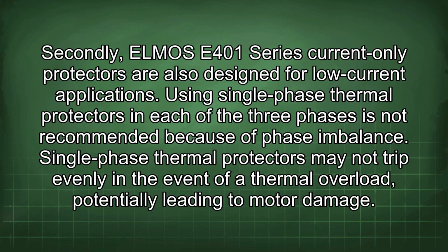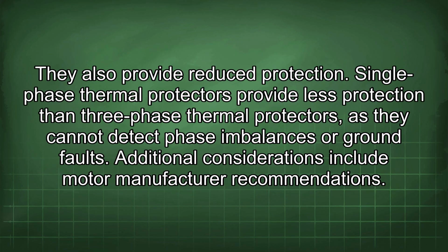Using single-phase thermal protectors in each of the three phases is not recommended because of phase imbalance. Single-phase thermal protectors may not trip evenly in the event of a thermal overload, potentially leading to motor damage. They also provide reduced protection. Single-phase thermal protectors provide less protection than three-phase thermal protectors, as they cannot detect phase imbalances or ground faults.